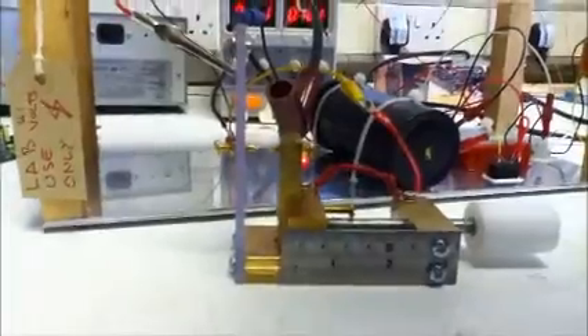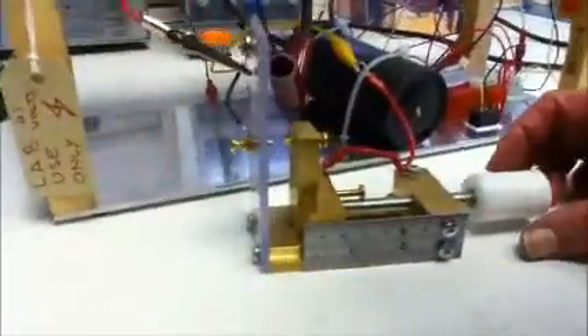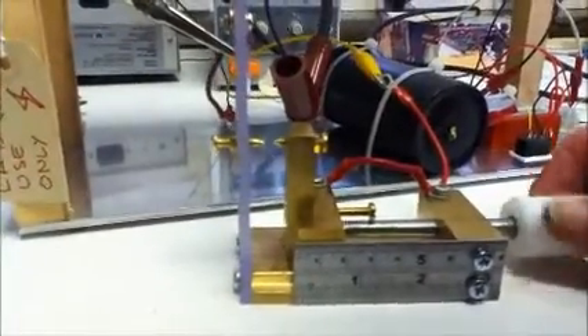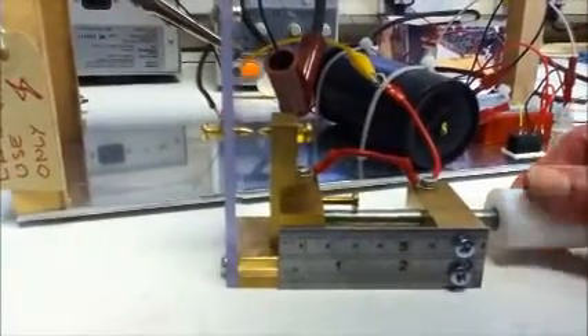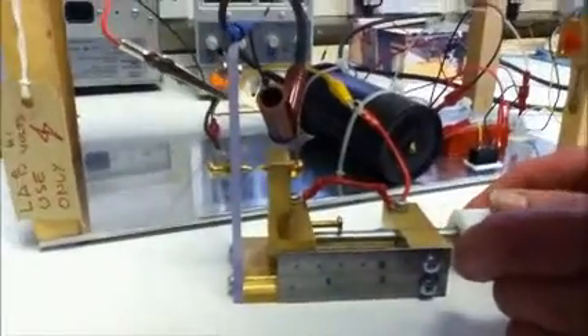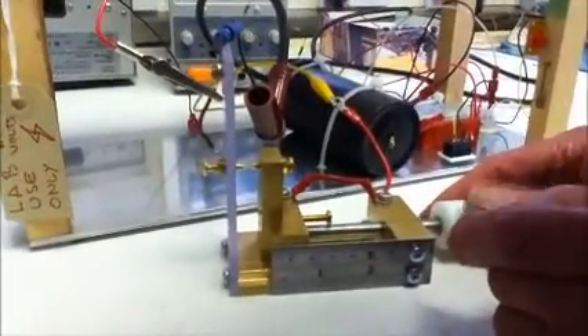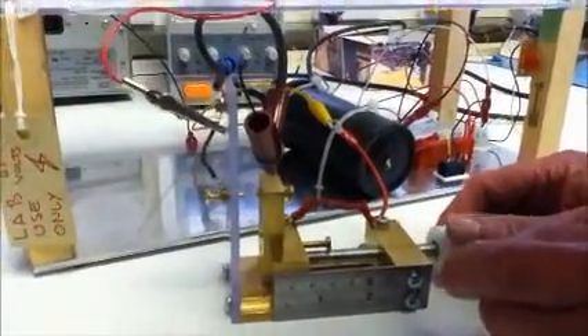Let me just turn the HT off before we do this. This gap here, we can crank this in and align and adjust these points so that at 0 on the millimetre scale they're just touching.